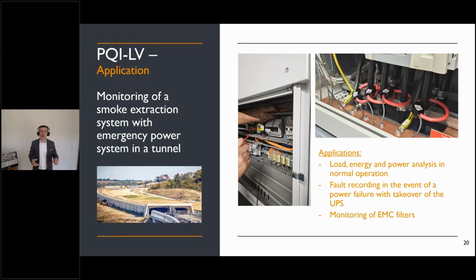At the same time, because we have an inverter installed, we have EMC filters installed. I don't know who knows that from your side, but even an EMC filter has a lifetime. We bring in a lot of EMC filters in the meanwhile, and sometimes it happens that the EMC filter is not working anymore, and you cannot see that. You can only see it directly in the current as well as voltage supraharmonic levels, and even for this application the device is installed. So we have here 3 applications with 1 device, and I think this is a great opportunity to save money.